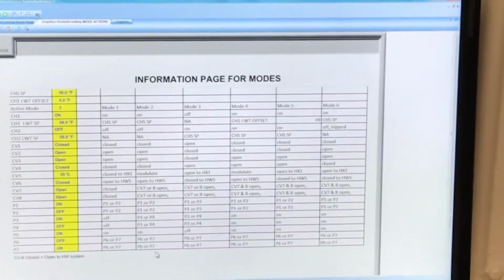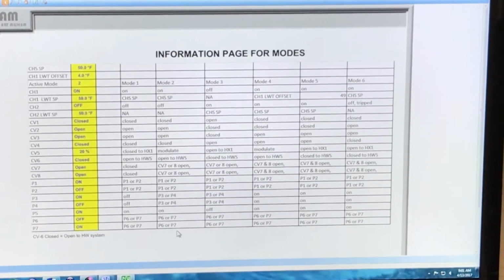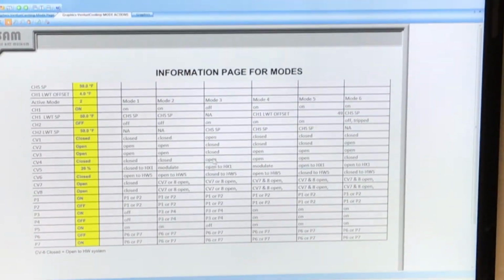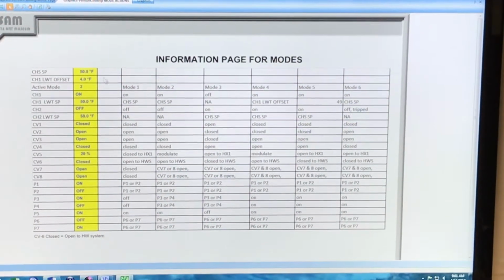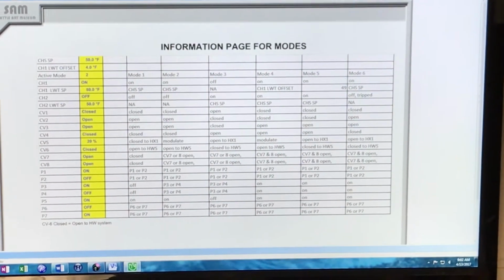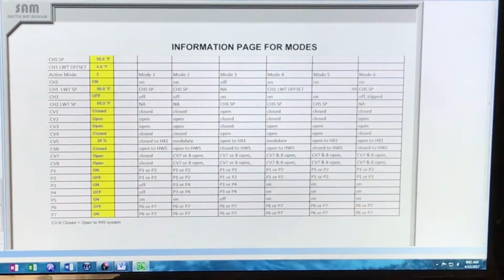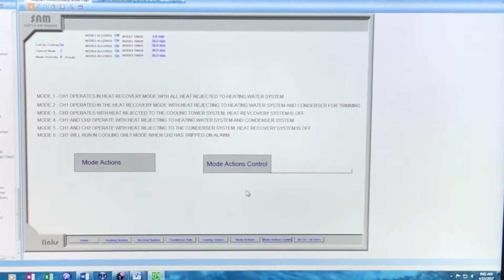You can see the flow, and then you can match it. If you try to go through the sequence, it will be more difficult. But going through this table, you can see exactly what will be positioned, and then you can see the flow. It's a good way to see if you have a failed valve. It's a good troubleshooting tool.